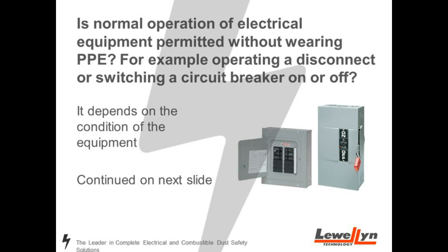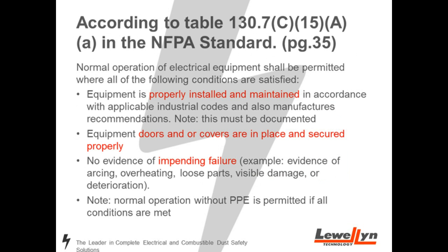They basically say that as long as you can satisfy three conditions, you can operate that switch or disconnect without wearing PPE. You have to make sure the equipment has been properly installed and maintained, that the doors and covers are in place and secured properly, and that there's no evidence of impending failure. The first two are pretty easy - properly installed and maintained, and doors and covers in place and secured. But impending failure? That one's a little tougher.